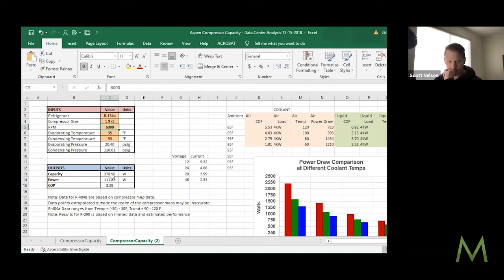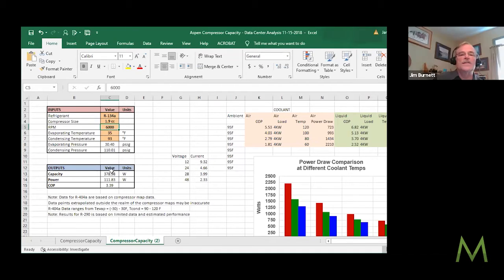So for this to get 380 watts of capacity, I know I can run my compressor at 6,500 RPM. We can use R134A, but we also have a whole range of new green refrigerants being required in the EU, and some customers are switching to those, some aren't. That system will do 400 watts of capacity at those temperatures.